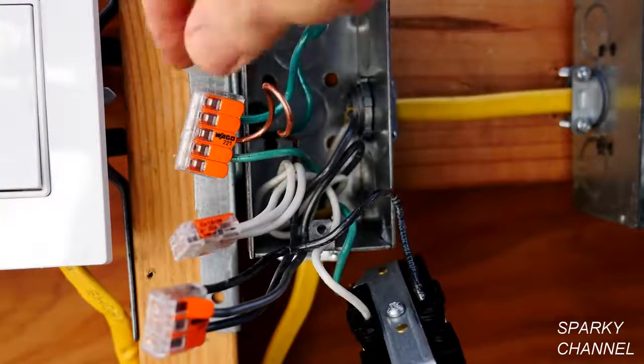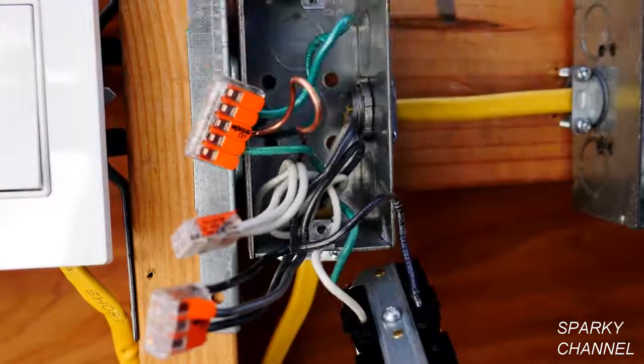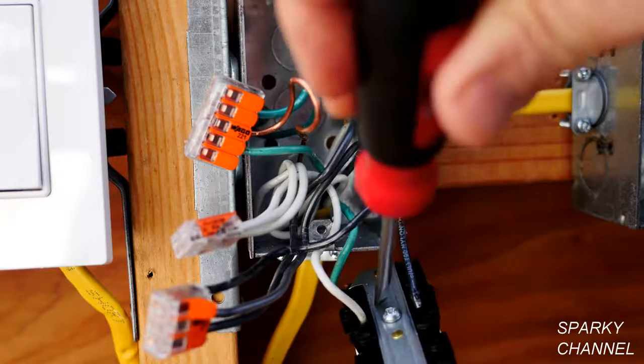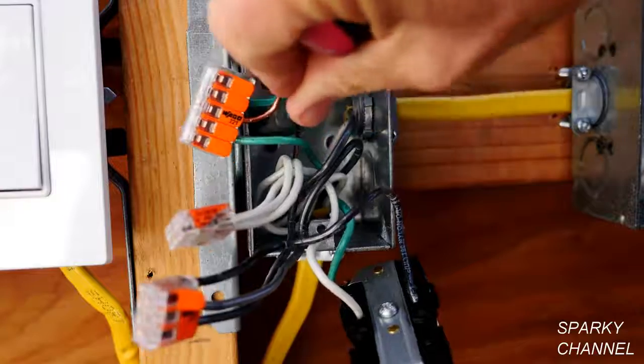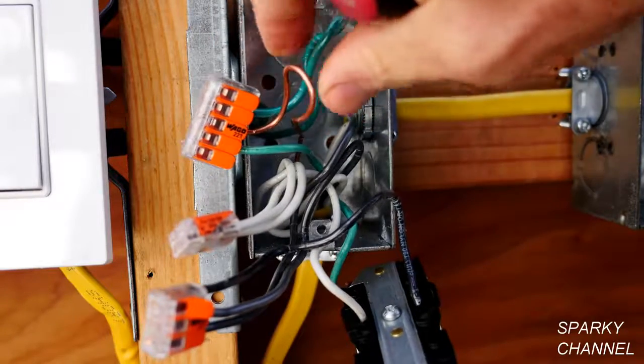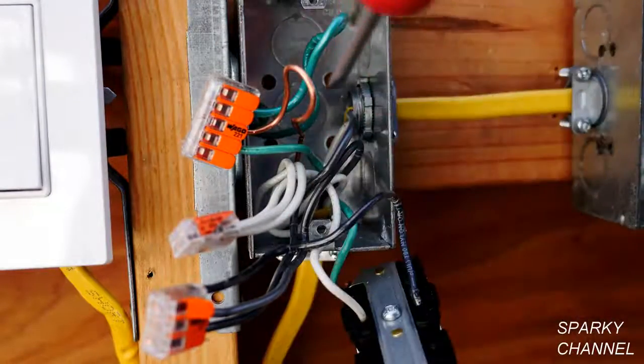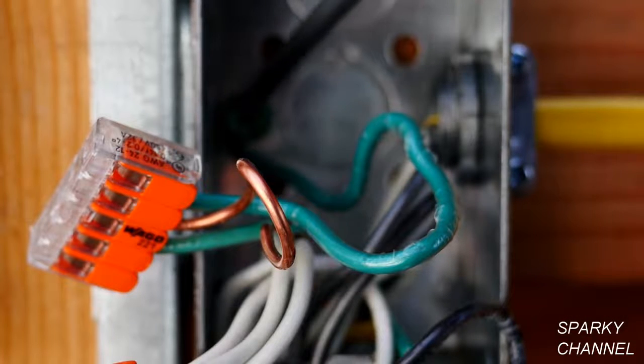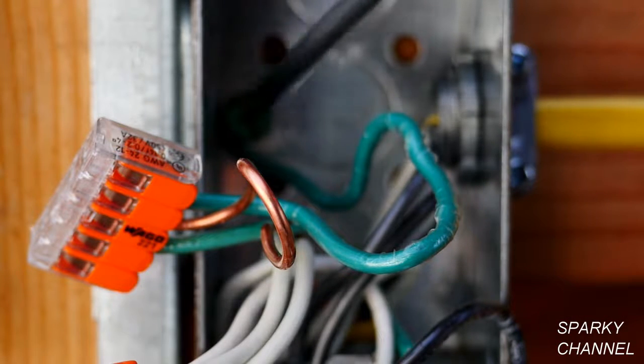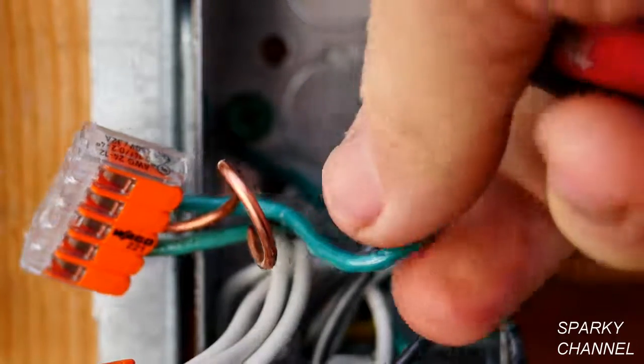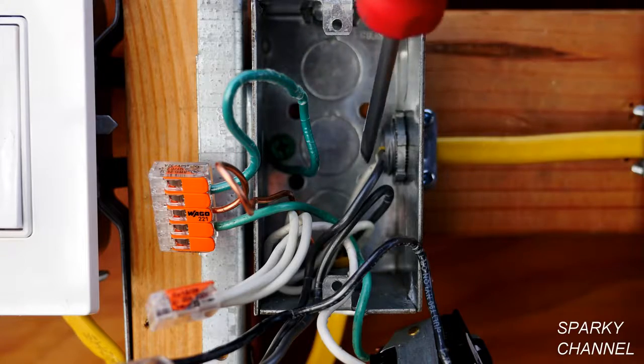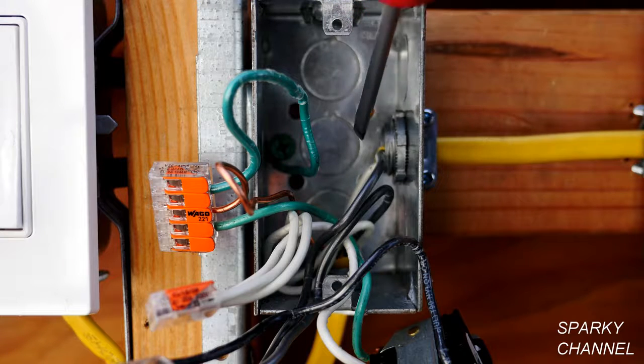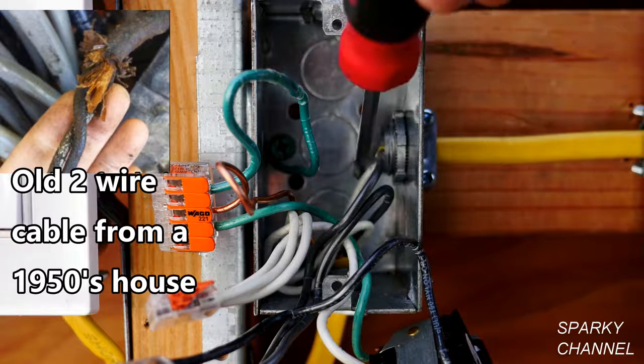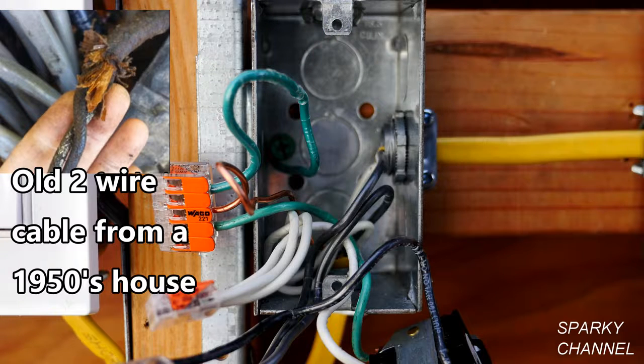Okay, here we have the grounds, and you can see we got one green wire going to the receptacle. We got one bare ground wire coming in from the power source, and we have one grounding pigtail right back here. It's called the equipment grounding conductor in the code book. There is no ground wire in this cable right here going to the next receptacle. So this is the problem. This is perhaps a two-wire cable that would be found in a 1950s, 1960s, or early 1970s house.